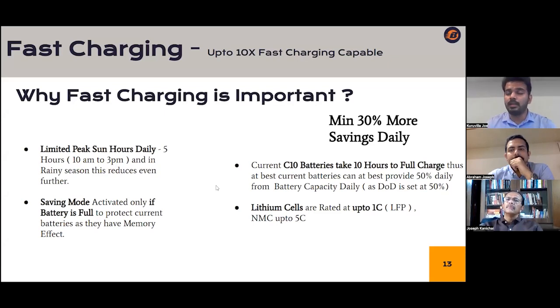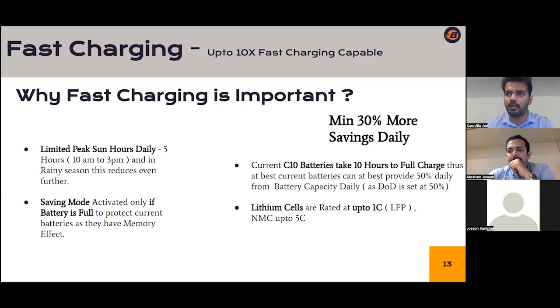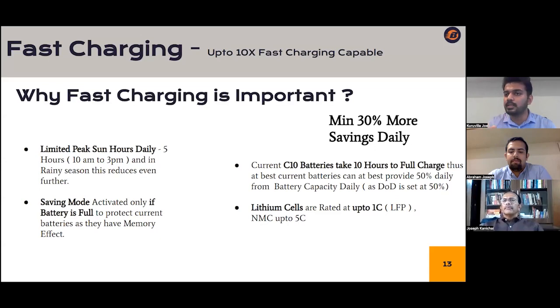So the ability—currently all the solar batteries being used are C10 rated lead acid tubular batteries. One of the important limitations is that a C10 rating means it takes around 10 hours to fully charge the battery. Now a limitation arises because in our region, like India, we are limited to around 5 peak solar sun hours daily. So we have to charge the battery within this limited 5 hours. That is why what is currently done is that the batteries are only restricted to be discharged up to 50%, which is why we mention a 50% DOD.